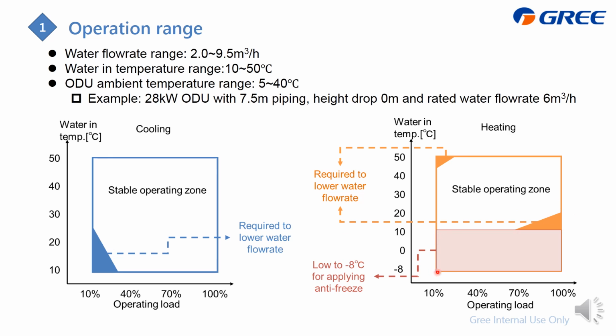And for this one, it means if the water in temperature is lower than 10 degrees, the system will lock down. But if you put some antifreeze into the water, which means to lower the freezing point from 0 to, for example, -2, -3, you can also lower this zone, and the lowest we can make it is -8 degrees, which is this one.